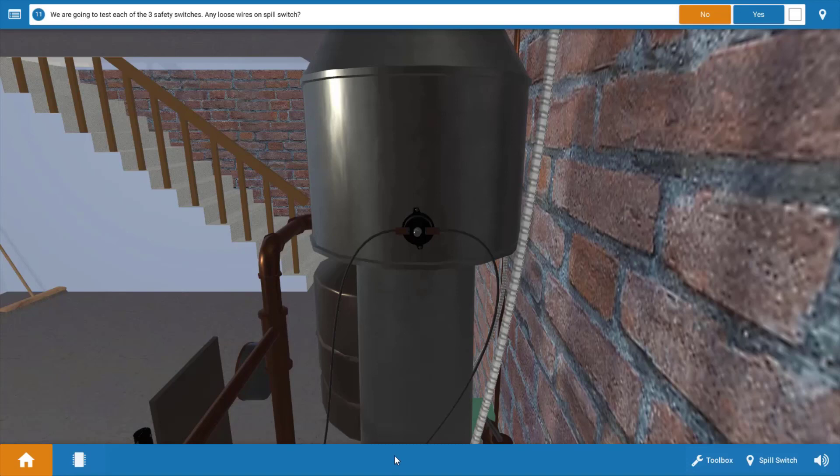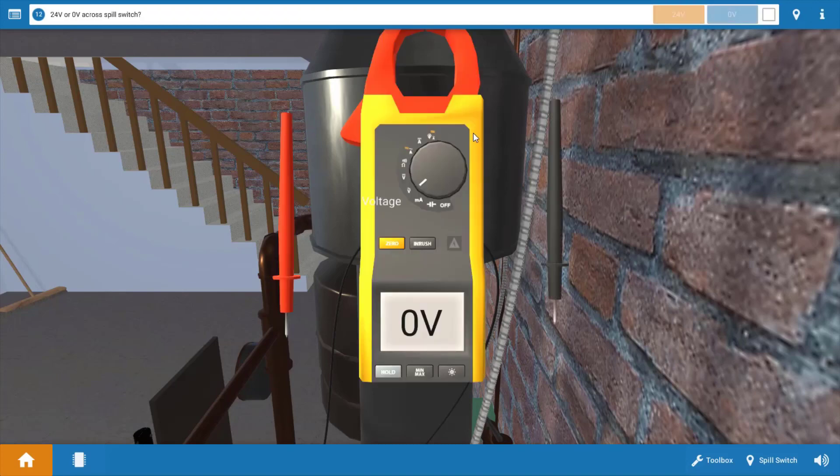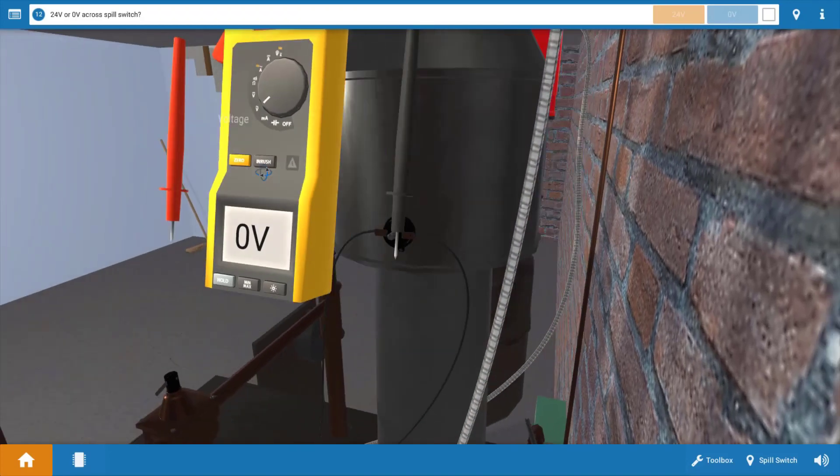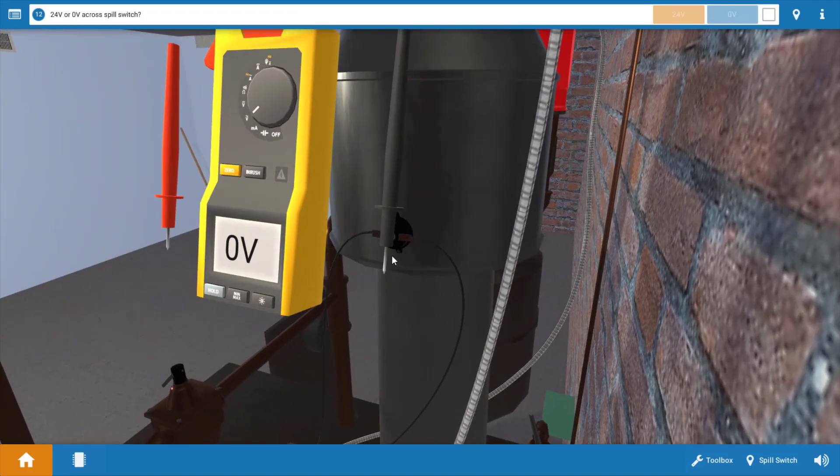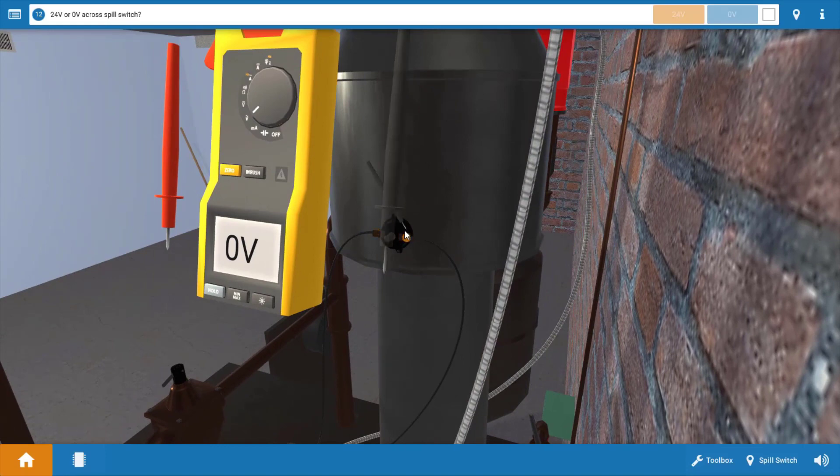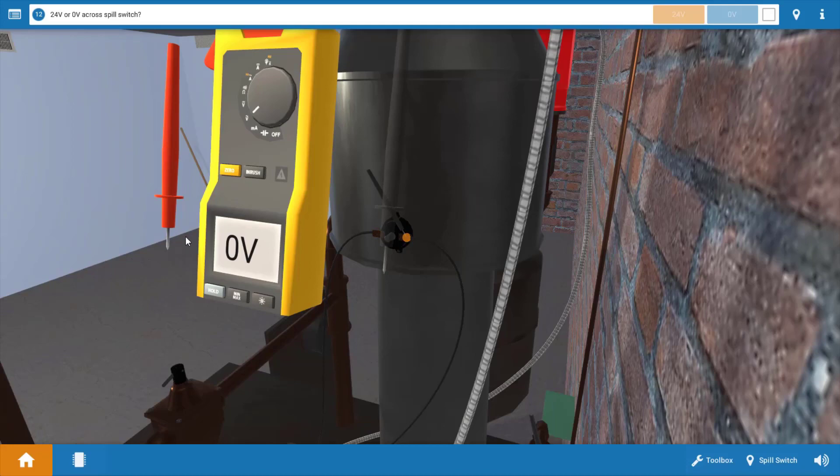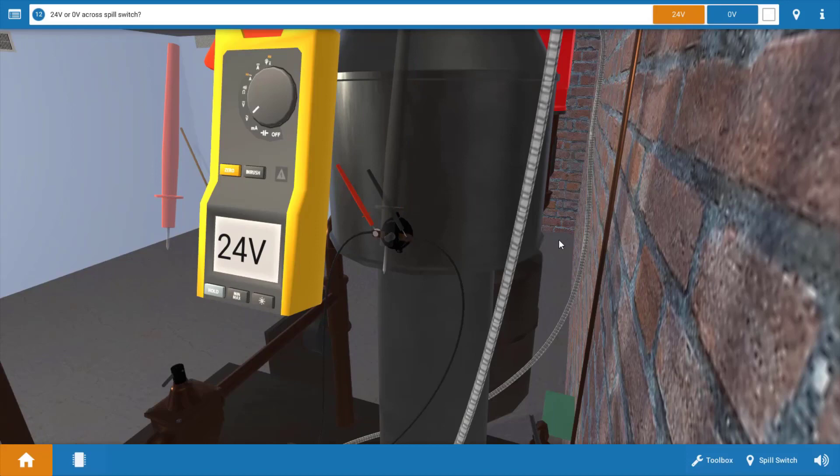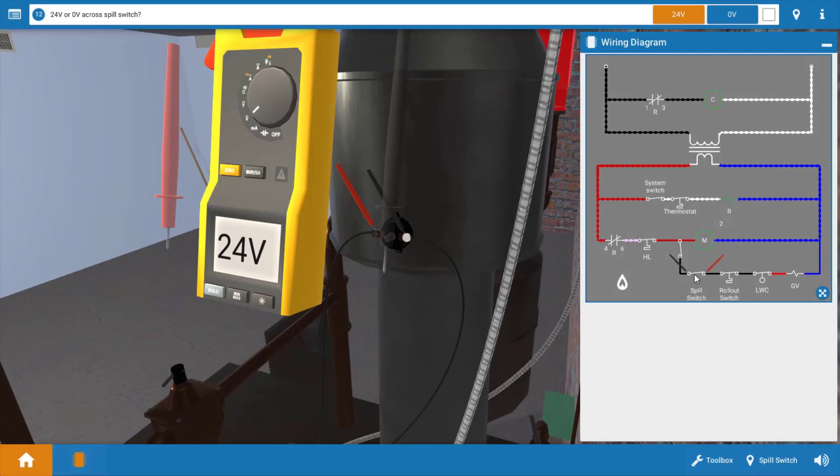First let's inspect for loose wires on the spill switch prior to checking that. As we can see the wiring connections appear to be secure. Next we're going to measure voltage across the contacts of the spill switch. We're going to place each of the leads at the glowing orange hot spots right across the normally closed contacts of the spill switch. When we do this we get 24 volts which means we have a difference in potential here across the spill switch and the spill switch is open. Let's review the wiring diagram for just a second here. We can see our leads placed across the spill switch and we've got 24 volts across it verifying that the spill switch is open.